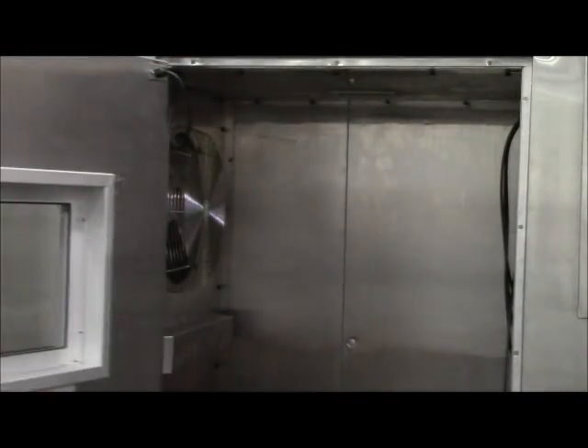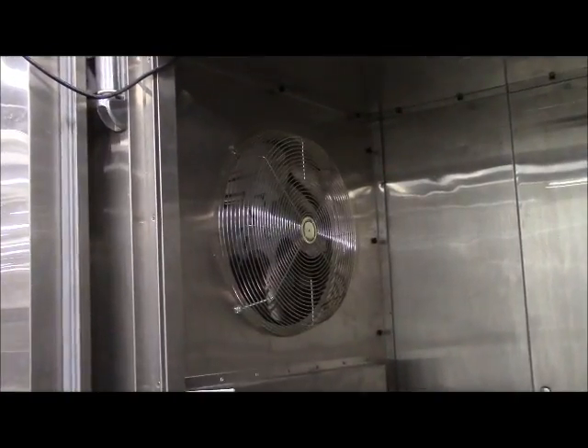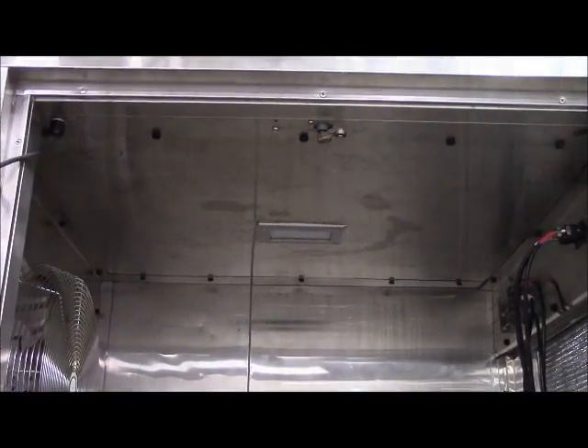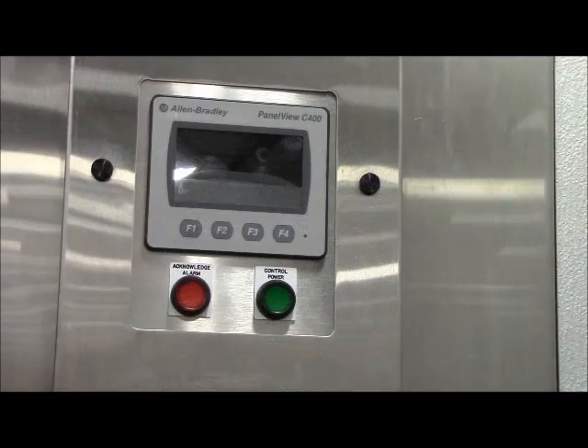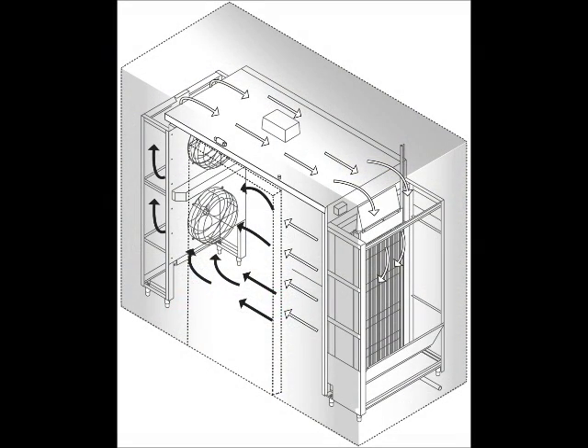With the door open, we see the major components of the blast chillers: the fans, the plenum, the coil, and the controller. These components drive the air in a circular pattern. The air is pulled through the chilling space and is pushed up to the plenum by the fans. It flows above the plenum to the coil side and is then chilled while passing through the coil, returning to the chilling space. This laminar cycling of air ensures that there are no warm spots in the cooling area.